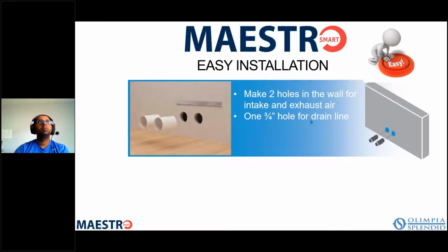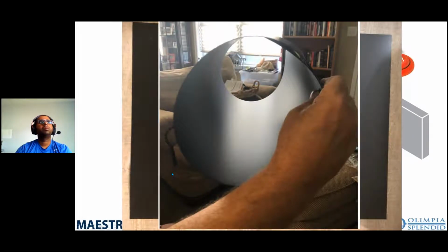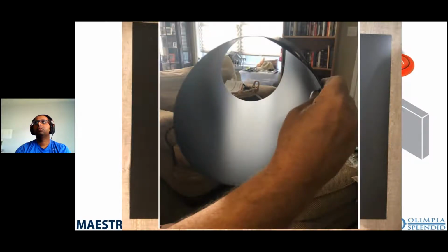So after you make those two holes, you put the bracket on the wall, and there you see the bracket on the wall, and then you have to install the ductwork. In other words, you have to have a duct that goes from the outside wall to the inside wall so that your air streams are isolated to just going into the condenser area and out of the condenser area. So you basically take ductwork and put it in the wall, and the ductwork ships with the unit. That's the ductwork. It's just a flat piece of composite plastic that rolls up, and there you have an 8-inch duct, okay?